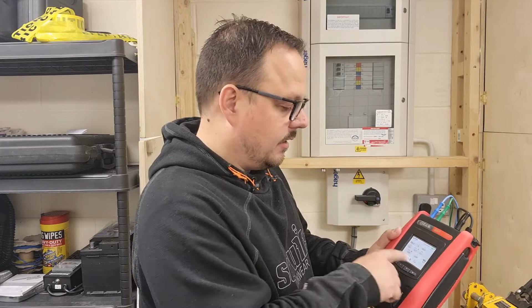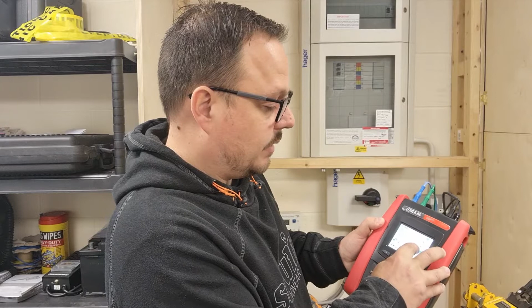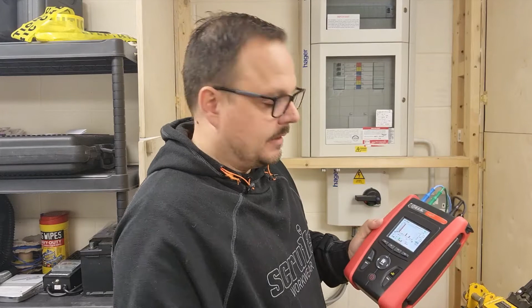If you go into the graph menu, you can see on there it does go down to the 25th, and that's all downloadable to the SD card, so you can transfer that information as well to the software that comes with a multifunction tester and have a play around with that on your laptop, desktop, and see exactly what's been recorded. So I mean, in a multifunction test instrument, to have some power quality analysis, it is quite good. I mean, it saves getting the data logger out and having a look at what's going on.